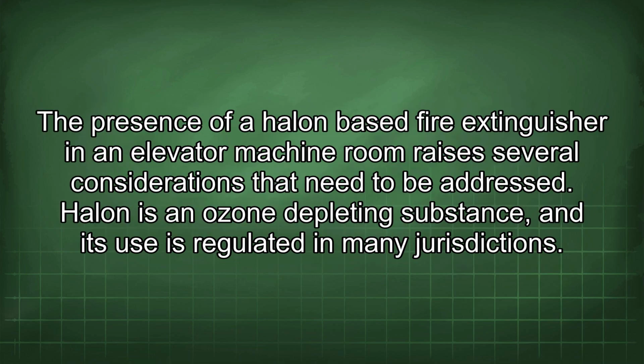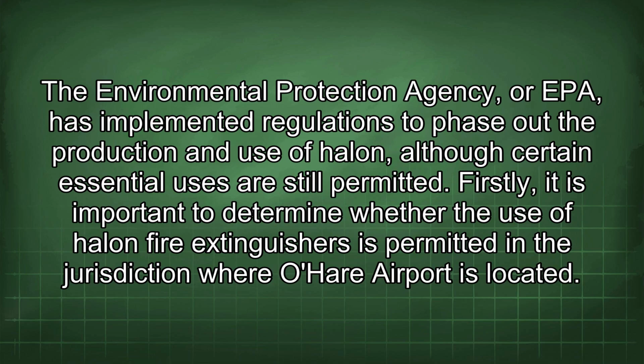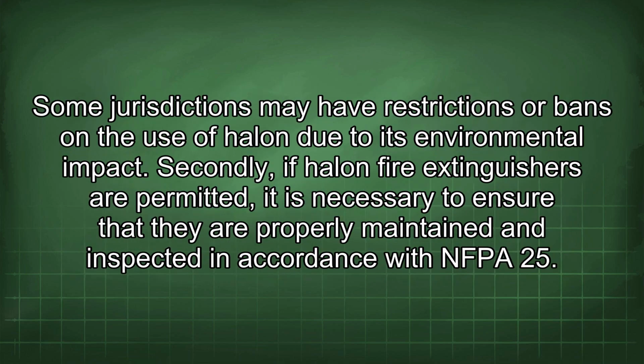The presence of a Halon-based fire extinguisher in an elevator machine room raises several considerations that need to be addressed. Halon is an ozone-depleting substance, and its use is regulated in many jurisdictions. The Environmental Protection Agency, or EPA, has implemented regulations to phase out the production and use of Halon, although certain essential uses are still permitted. Firstly, it is important to determine whether the use of Halon fire extinguishers is permitted in the jurisdiction where O'Hare Airport is located. Some jurisdictions may have restrictions or bans on the use of Halon due to its environmental impact.